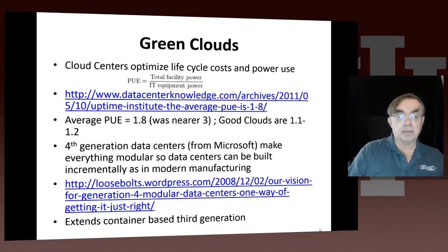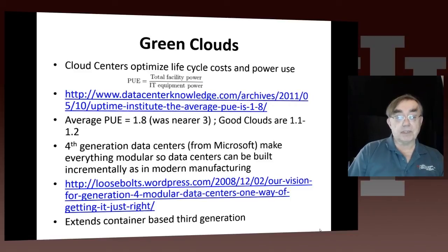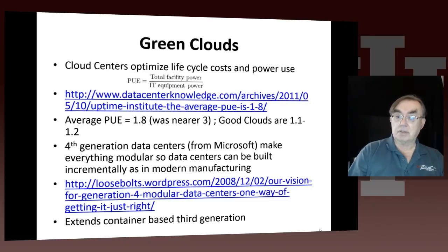Here's some comment on greenness. There is an important metric called the PUE — total facility power over IT equipment power. If it were one, all your power would go into computing and storing data. But if the PUE was 1.8, which was the average a couple of years ago, then 40% of power is wasted. Clouds are much more efficient — they only waste about 10 to 20% of power, with a PUE between 1.1 and 1.2. Clouds have pioneered the fact that data centers can be made much more efficiently.